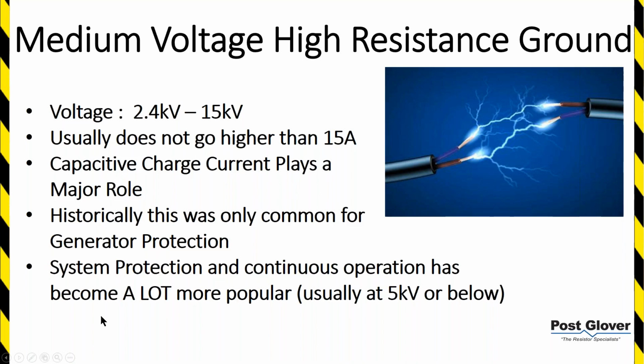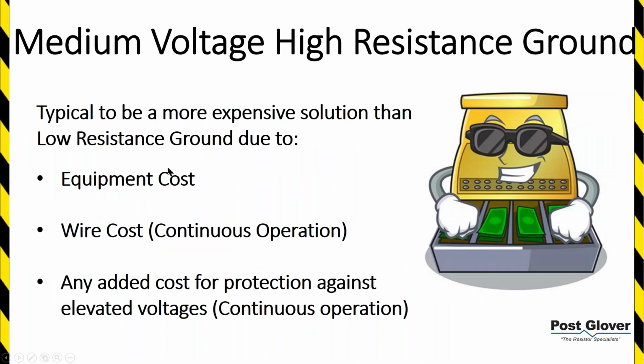So, okay, let's move forward here. It's typically a more expensive solution than low resistance ground. Essentially, you have monitoring equipment. You have a lower current, so you're usually going to have a larger enclosure. So the equipment cost is going to be higher, depending on how long you're going to be trying to go without tripping. You're going to have additional wire costs. We'll go over that standard in a second. And any added cost for protection against elevated voltages. So there's added cost in medium voltage high resistance ground. So you might be asking yourself, why is it that you just told us that it's getting more popular? Why is it so much more expensive?